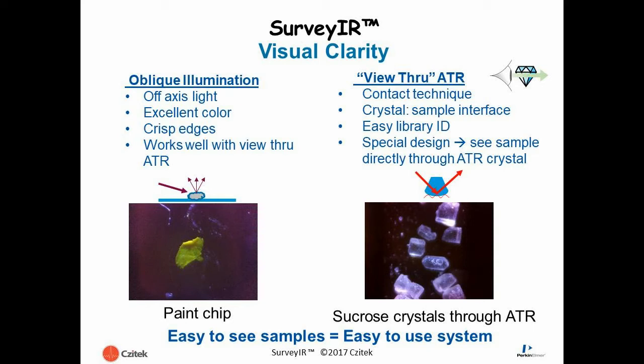A unique feature of SurveyIR is the ability to observe specimens through the diamond internal reflection element and also observe contact with the sample. Attenuated total reflection spectroscopy is a contact method which provides ease of use and simplicity in the measurement. Samples can be identified through searching of library spectra, as with other infrared spectroscopic methods.